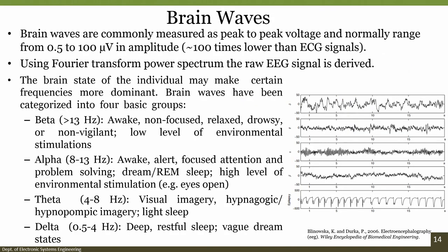So if we talk about brain waves, they are commonly measured as peak to peak voltage, with a normal range from 0.5 to 100 microvolts. Now, if you see ECG or EMG, the voltage is really high, but when you talk about EEG, we are looking at some microvolts of signal, which is approximately 100 times smaller than the ECG signal.